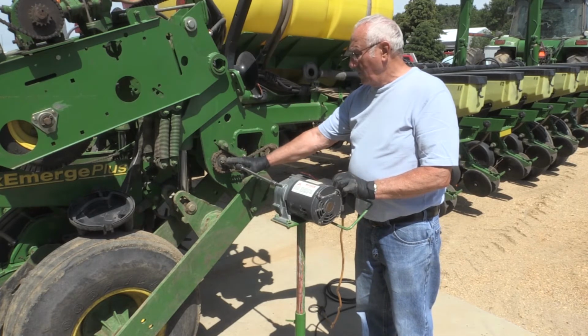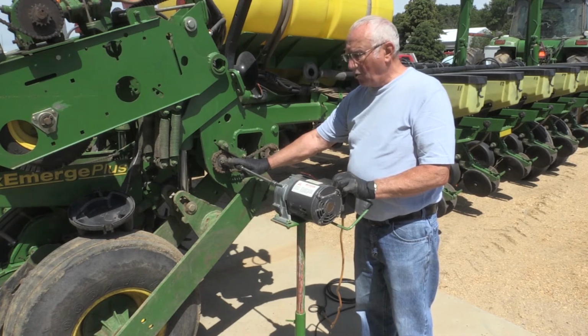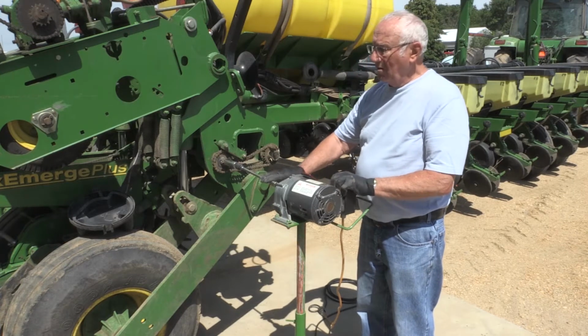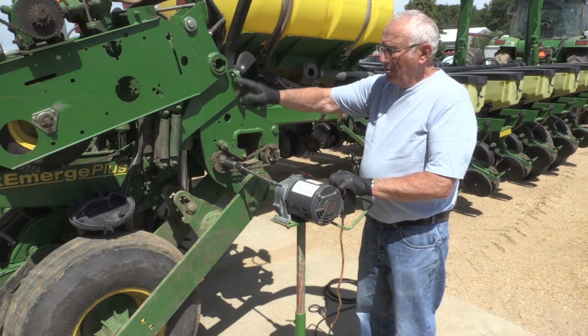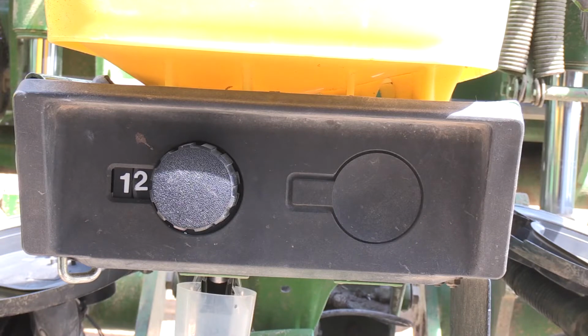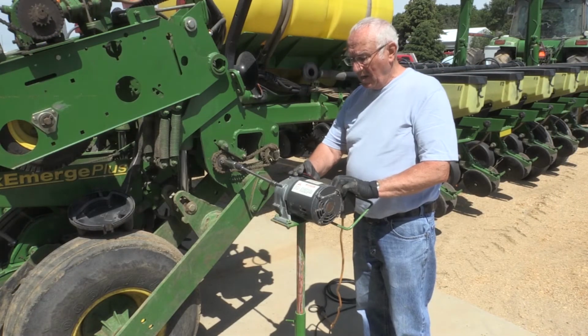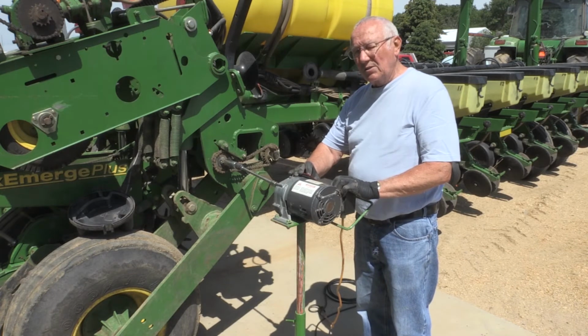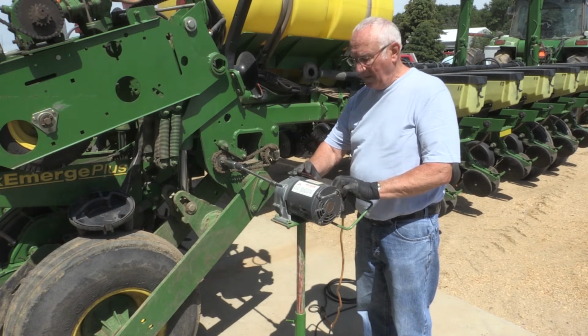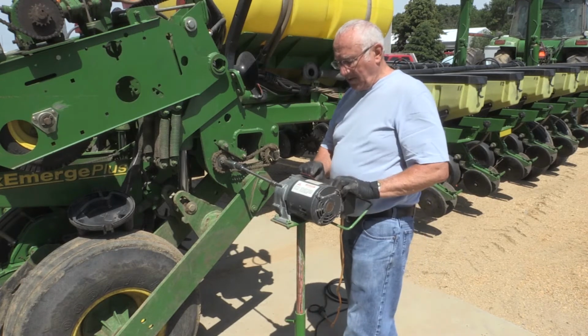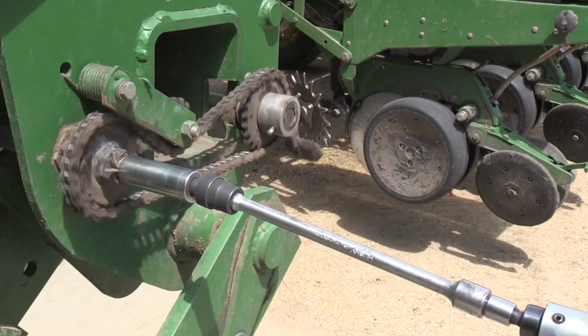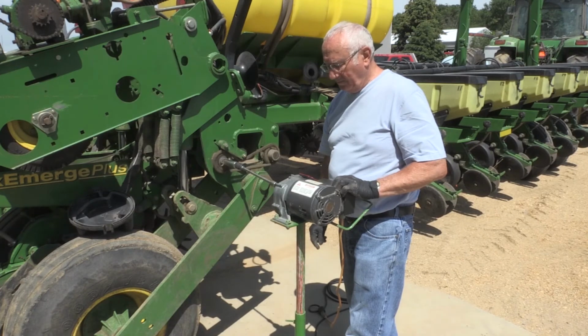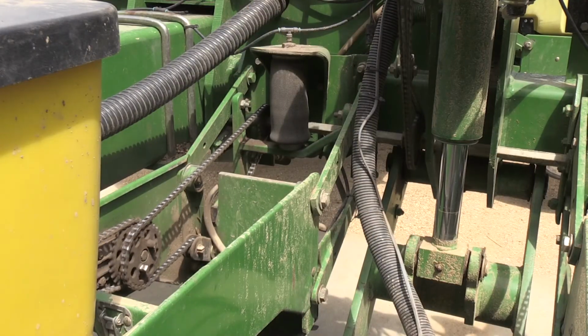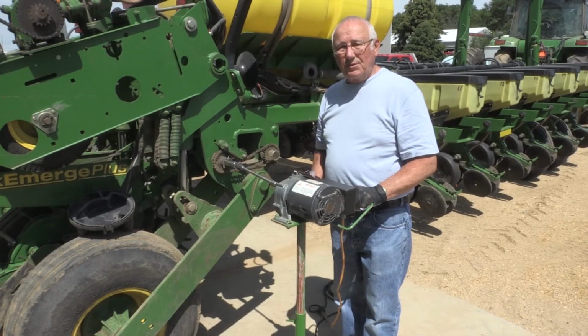We've got our shaft hooked up and driving in the correct position, and we set it on number 12. This is just an estimate, and what I usually do is start with 2 rows first to see how close the calibration is going to be. So we'll run it here now for 62 seconds. There we have it. We're at 62 seconds.